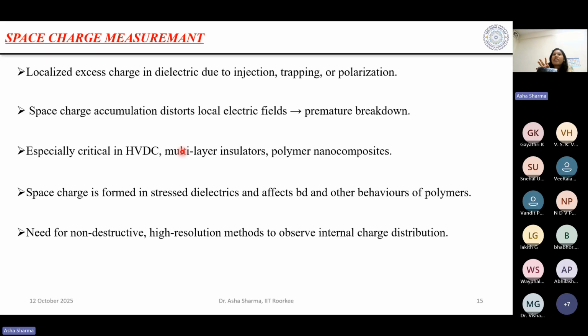The reason is, let's say I have applied 10 kilovolt to a 1 meter XLPE cable, so we will say 10 kilovolt per meter will be the dielectric strength of my cable. But if space charge is adding to the main field, let's say it is producing 1 kilovolt, then this 10 kilovolt will be added to this 1 kilovolt. So now it will be 11 kV. So within the material itself, instead of 10 kV per meter, it will experience 11 kV per meter. So that's an issue. Again, the problem is mostly happening within the HVDC.